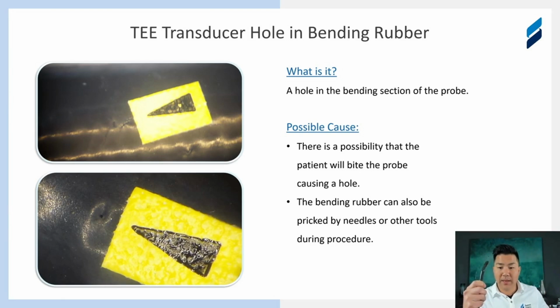And so we recommend that the sterilization department really look, bend it, and articulate the bending rubber section, giving it a really close eye underneath a magnifying glass to catch this. Early detection here is really important. Oftentimes, if there's some fluid ingress, it's not catastrophic, very repairable. And if you catch it really early, we can take it apart very quickly, replace the bending rubber with a new one, and clean out all of the acidic fluids on the inside to prevent the corrosion. And for a very inexpensive repair, you just save the probe and really extend the life.